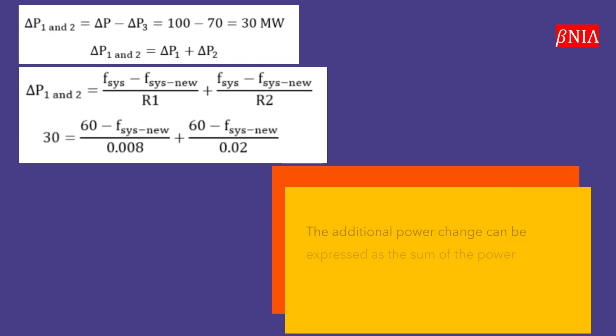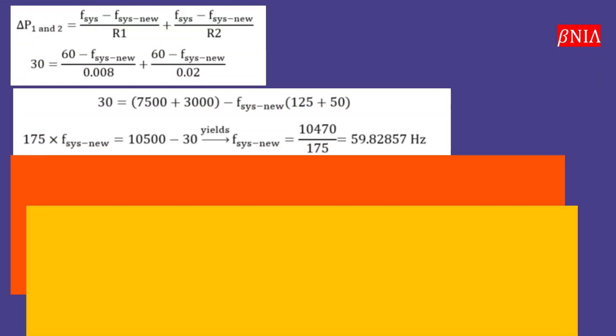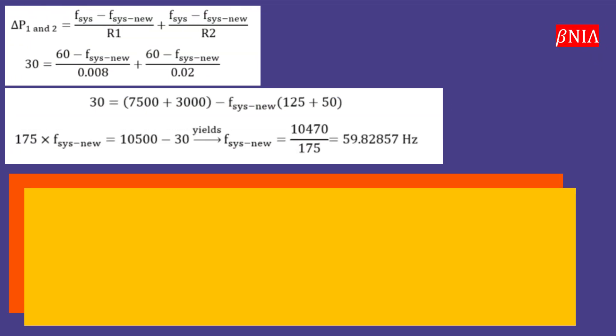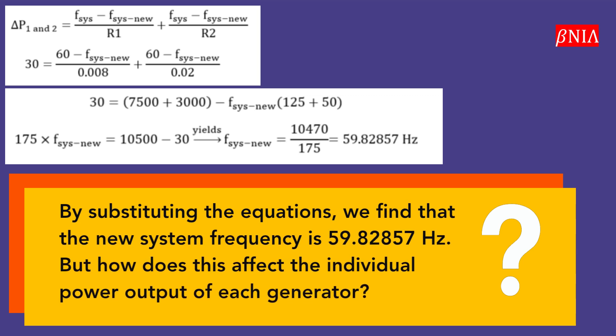The additional power change can be expressed as the sum of the power changes for the first and second generators. Keep in mind that when the load increases, all generators operate at the same reduced frequency. By substituting the equations, we find that the new system frequency is 59.82857 Hz.